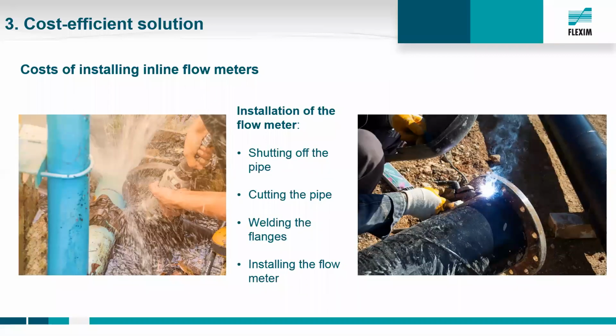Afterwards, for sure, the major part is the installation. The installation of the flow meter also differs. On an inline meter, usually you have to shut off the pipe, or excavate, depending on whether it is buried or not, cut the pipe, weld flanges, and install the flow meter. That is when we consider a new installation. If you do a one-by-one replacement, then it might differ, but now we are considering a new installation, so we have to cut the pipe, weld the flanges, and install the flow meter.